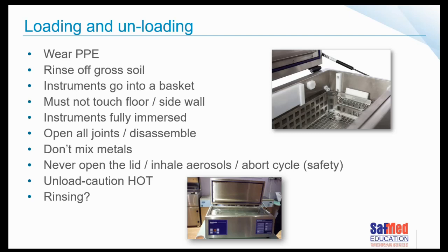The lid is meant to be on through the duration of the cycle while all those bubbles are going. You're aerolizing microorganisms, you're going to inhale them, and you're going to contaminate the environment around the machine. Remember, we spoke about that last week. Some of them have safety mechanisms so that if you open the lid, the cycle will abort immediately, and that could waste a ton of water and detergent for no good reason. It might say press the button to pause the cycle, then open the lid. So again, read the instructions for use and get your in-service training.